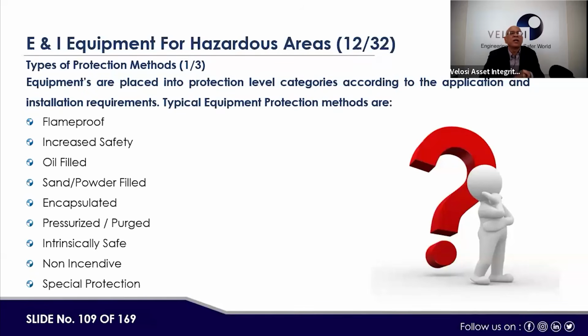Then the second thing is the type of protection methods. For example, if we have to see the next, what kind of protection we need. First is EPL, then the protection: flameproof, increased safety, oil filled, sand or powder filled, encapsulated, then pressurized or purged, intrinsically safe, non-incendive, or special. The same example, what kind of protection, these are explained here.